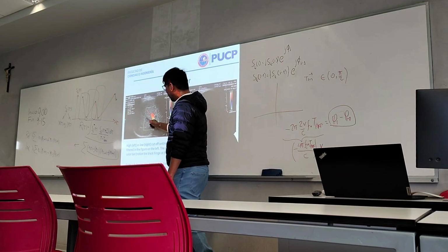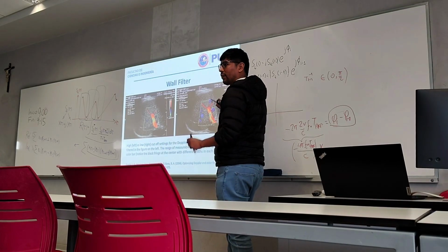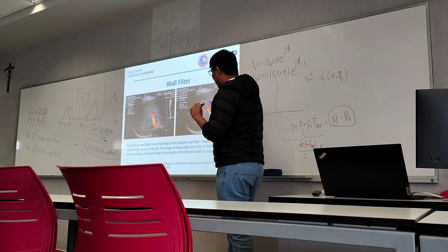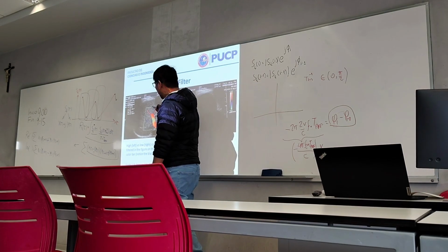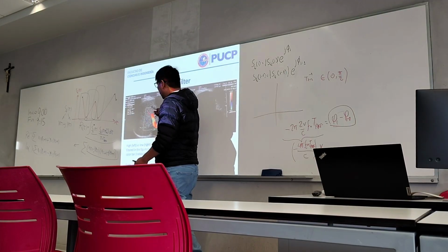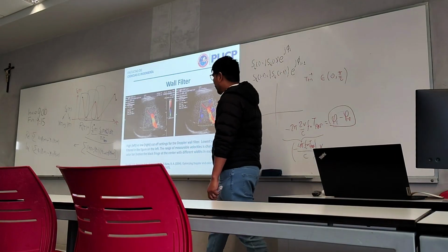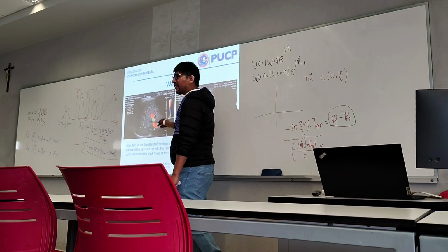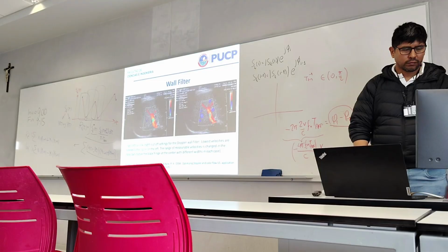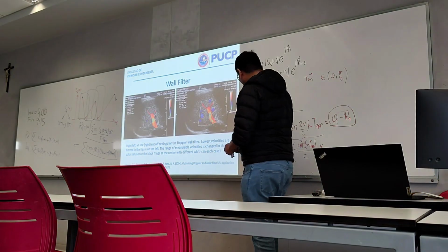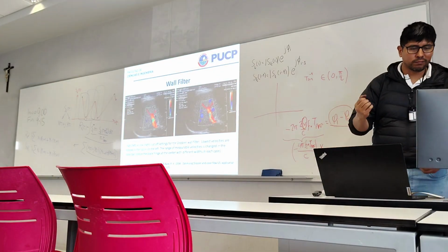it won't show. So the particles with a slow velocity, like for example here, there was some movement. Slow velocity. The cutoff frequency here was low, so we can detect that. But here, the cutoff frequency was higher, so we need more velocity shown in the Doppler. So like here, only the strong area will show us movement of vessels. These blue and red values correspond actually to this V, the particle velocity that we want to calculate.